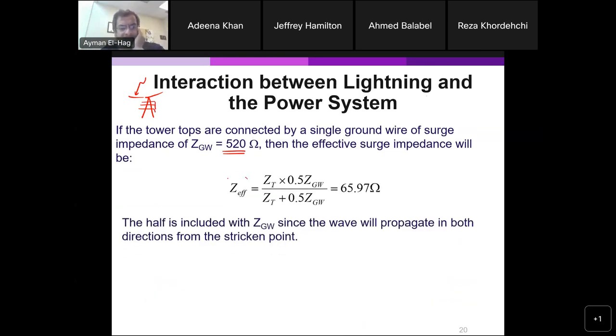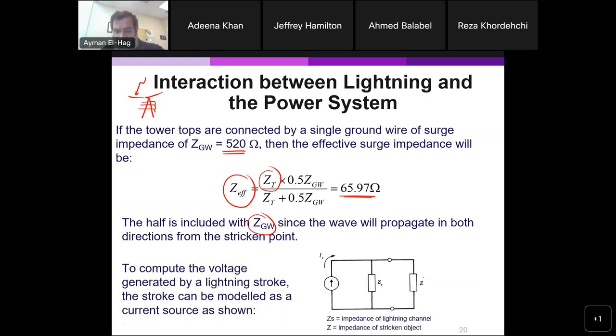You will now have a total Z effective, which is the ZT, the surge impedance of the tower, plus 0.5, because the waveform is split: half of it will go to the right, the other half will go to the left. So we consider only half of the ground wire impedance. So it will be in parallel with the ZT, and you will have a total Z. This is what is seen by the surge current. So when the surge current comes here, it will see this Z. This is the impedance of the object that has been struck.